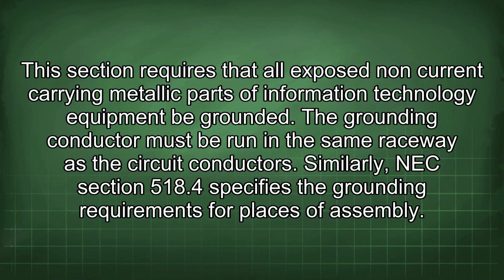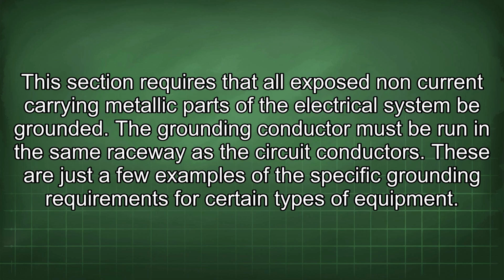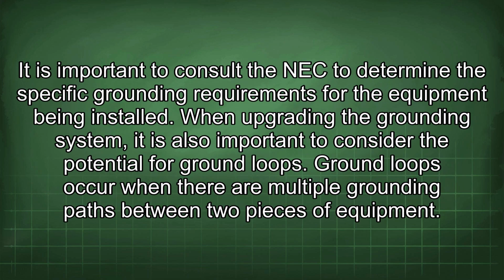Similarly, NEC Section 518.4 specifies the grounding requirements for places of assembly. This section requires that all exposed non-current carrying metallic parts of the electrical system be grounded. The grounding conductor must be run in the same raceway as the circuit conductors. These are just a few examples of the specific grounding requirements for certain types of equipment. It is important to consult the NEC to determine the specific grounding requirements for the equipment being installed.